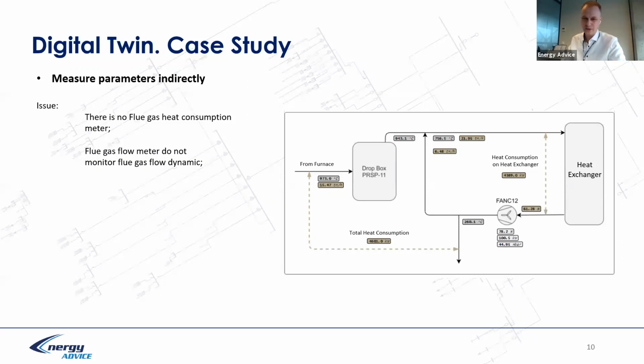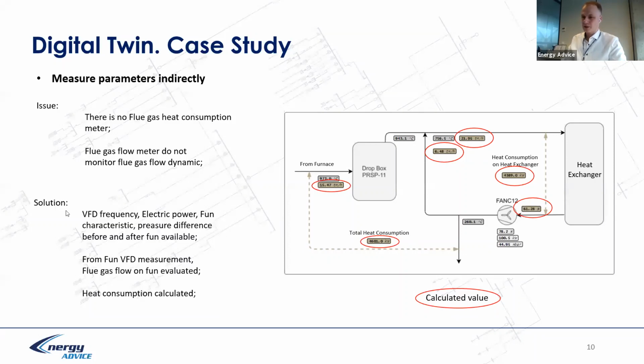Evaluating the density of the flue gas, we understand the mass of the flue gas. We calculate the recirculation flow and the consumption from the furnace. So we understand the heat consumption on the heat exchanger, and the total heat consumption for this unit. These values are calculated each 5 minutes. So the solution is the variable frequency drive, electric power, fan characteristic, and pressure difference. If all this data is available, we can evaluate the mass flow and calculate the heat consumption in this scheme.